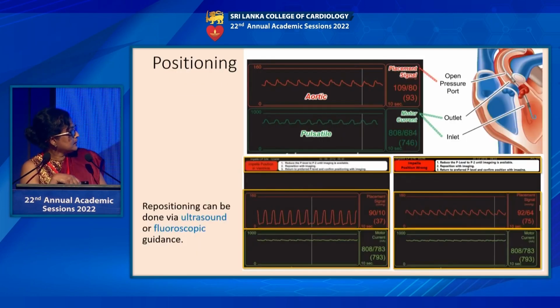So one of the monitors would look like this. It shows the motor current, which looks like a pulsatile waveform, and this is the blood pressure. If the motor current is getting flat, that means it has moved—it has to have this pulsatile-looking waveform.